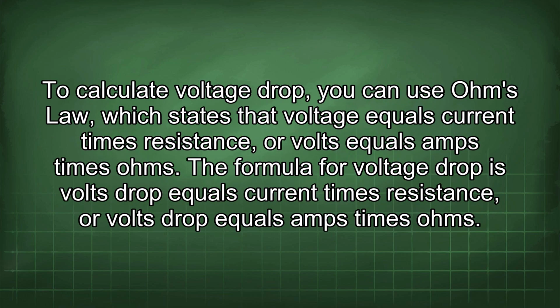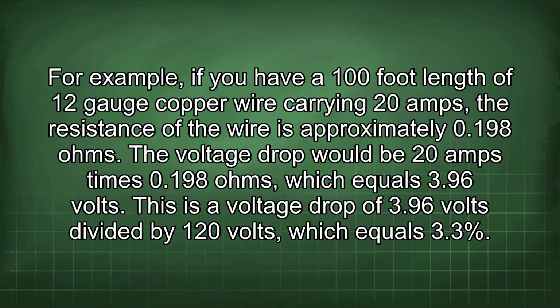To calculate voltage drop, you can use Ohm's law, which states that voltage equals current times resistance, or volts equals amps times ohms. The formula for voltage drop is volts drop equals current times resistance, or volts drop equals amps times ohms. For example, if you have a 100-foot length of 12-gauge copper wire carrying 20 amps, the resistance of the wire is approximately 0.198 ohms. The voltage drop would be 20 amps times 0.198 ohms, which equals 3.96 volts. This is a voltage drop of 3.96 volts divided by 120 volts, which equals 3.3%.